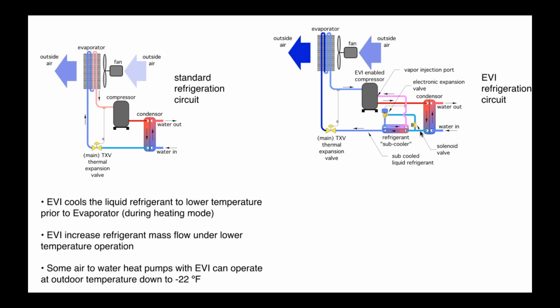There actually are some air-to-water heat pumps on the North American market now that can operate as low as minus 22 degrees Fahrenheit. So extreme cold conditions. Now, I'm not going to tell you you're going to get a COP of 3 or 4 under those conditions. You're not. You're probably going to see COPs in a range of maybe 1.2, 1.4. But remember, those conditions are extreme. They don't last very long in most areas, especially southern areas in Canada. Yeah, Yellowknife, probably if you see several days every winter.